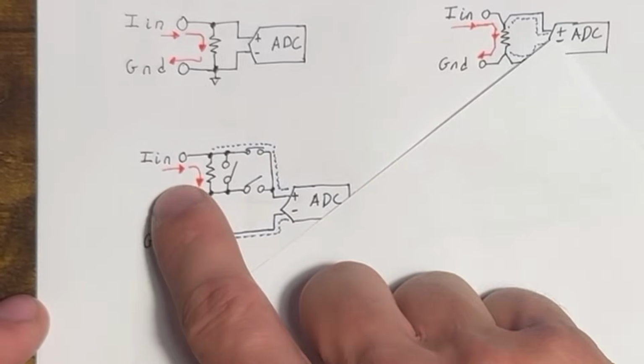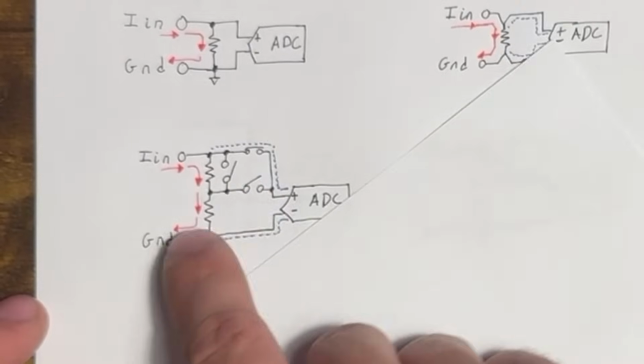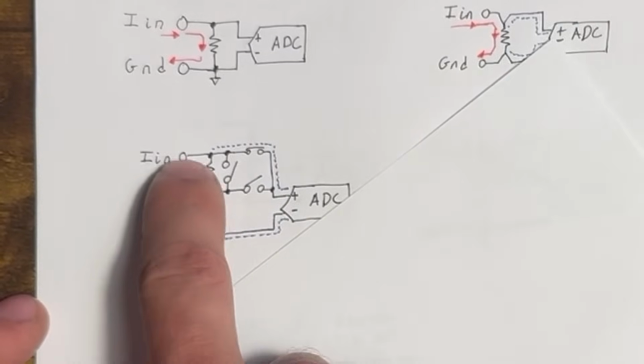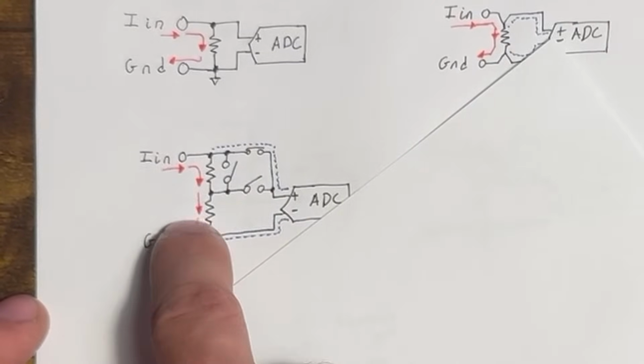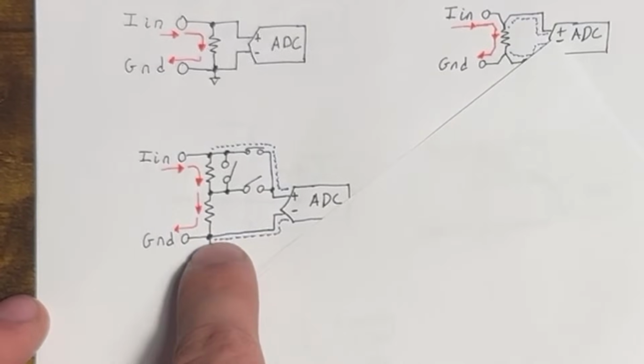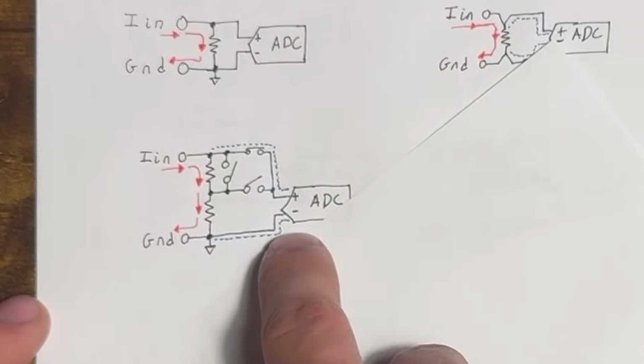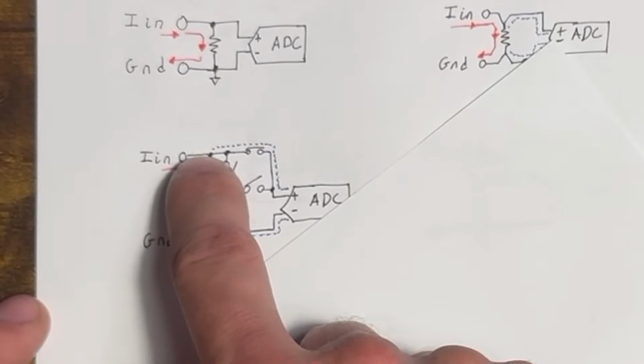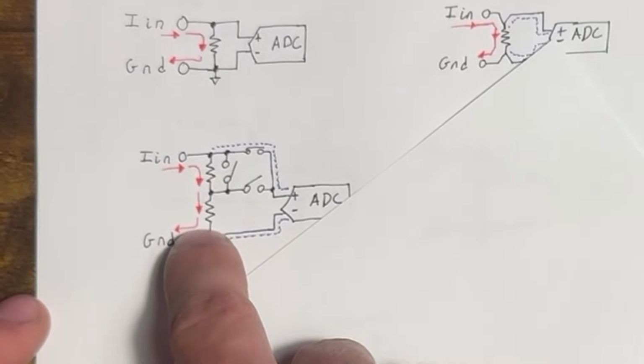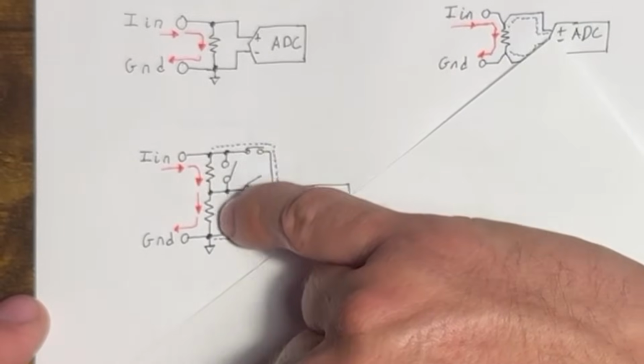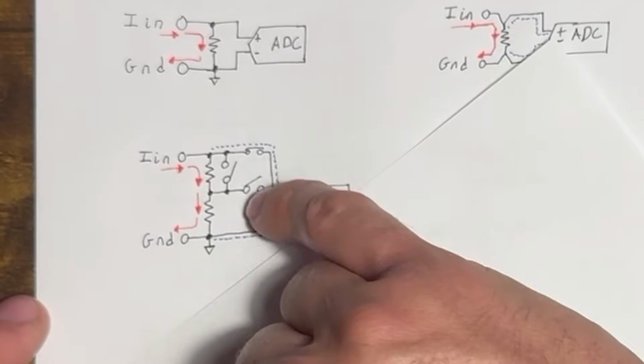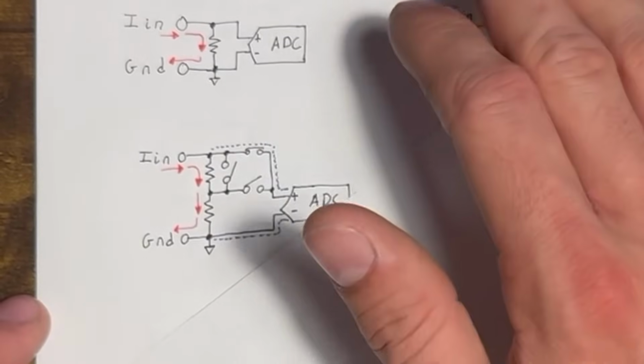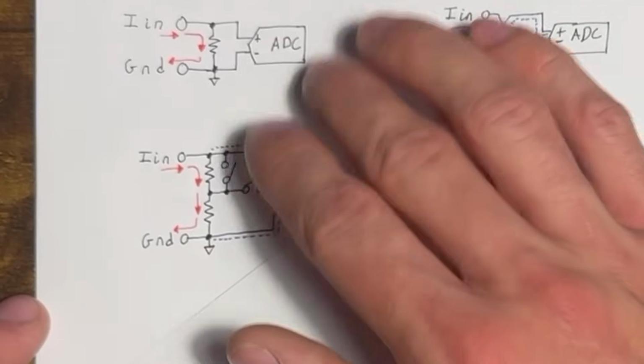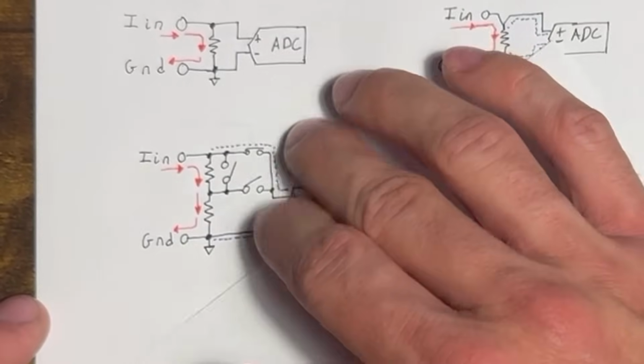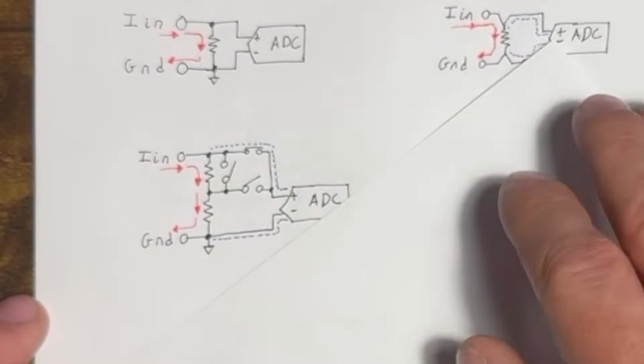So this is the resistor for milliamps, and this is the resistor for microamps. When set up in the microamp range, shown here, we have a switch open across this resistor, so current flows through both in series, and we measure voltage from ground to the positive side of this resistor. Because these two are connected directly in series, we don't have to worry about leakages or losses in the switches, which is nice. Again, much like with our high current range, we measure the voltage across there, and that divided by the resistance gives us our current.